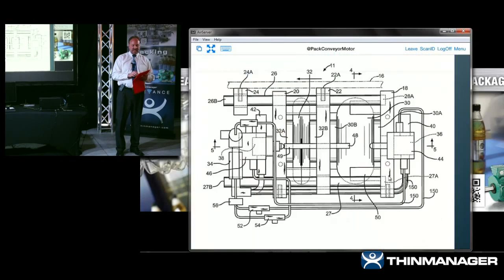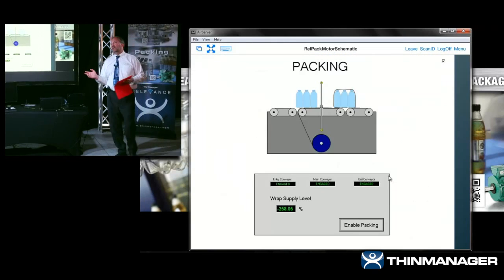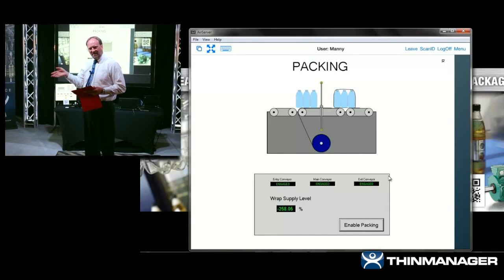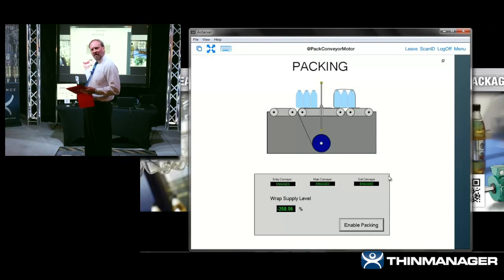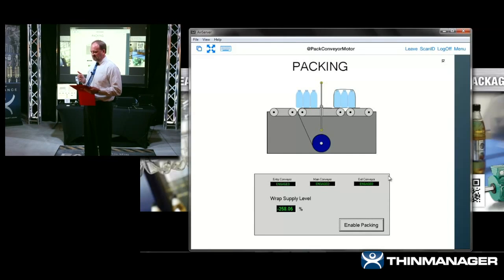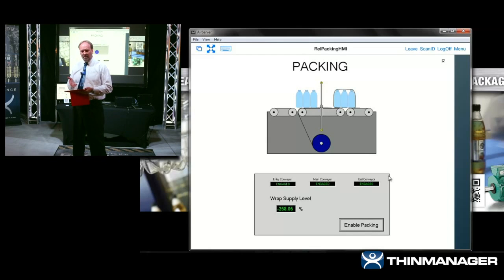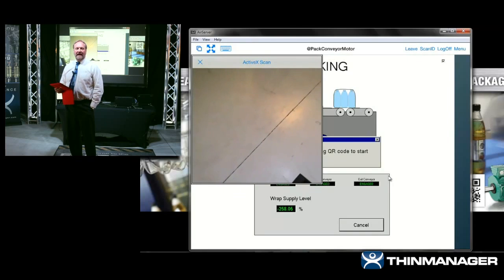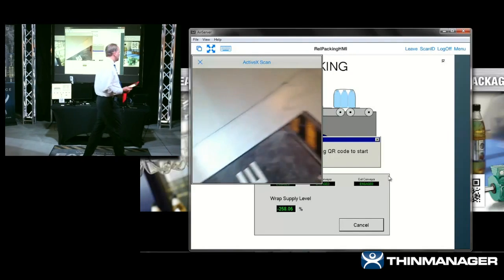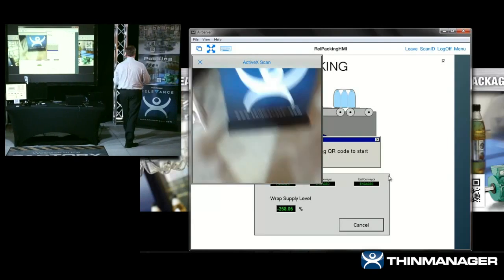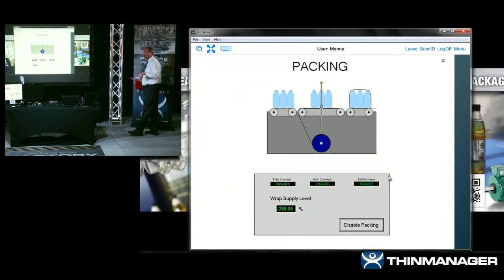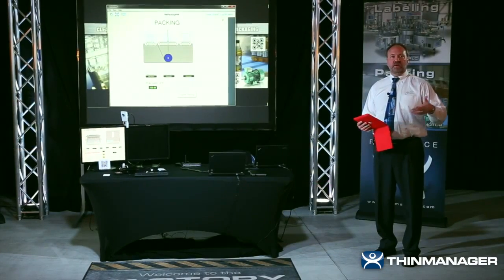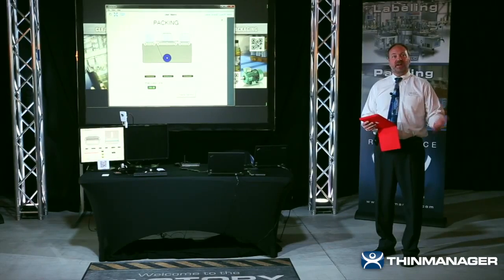After fixing the problem, Manny needs to re-enable packing and clear the faults so the operator can use it. He thinks he'll just do it from his device — but with the ActiveX control, we've put in a gate that says no, you have to scan the code on the machine to re-enable it. You have to be at the location you're trying to enable. That's a good example of where you can use the ActiveX control to provide a safety measure.